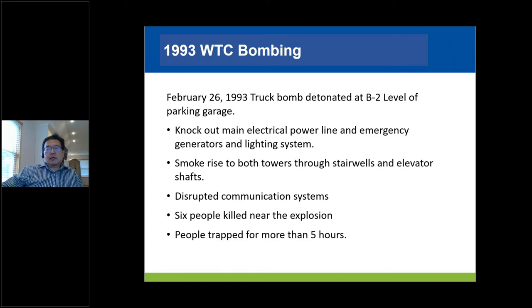That explosion knocked out the main electrical power lines and emergency generator in the building. The emergency generator was not knocked out per se, but because the cooling water system in the basement had its line broken, the emergency generators only worked for a very short period of time. And because of the explosion, the smoke was traveling through the stairwells as well as the elevator shaft to the tower, causing a very long, slow evacuation for the occupants in the towers. The explosion also disrupted the communication system.